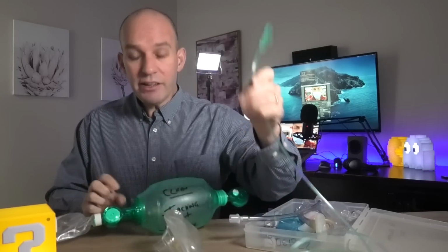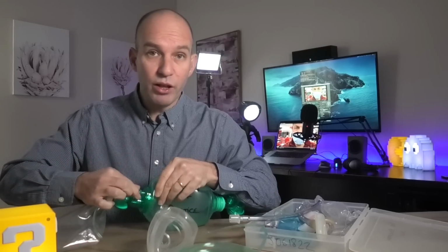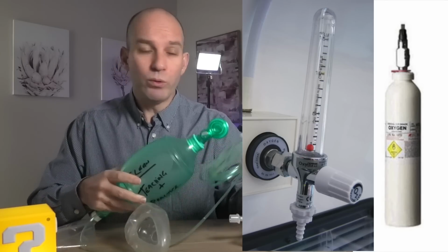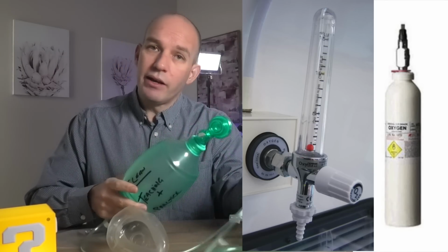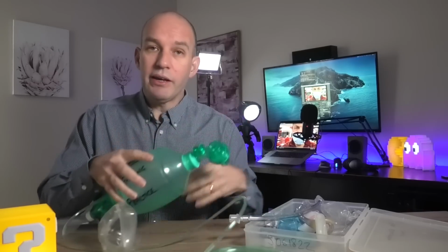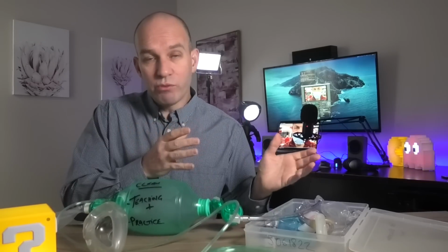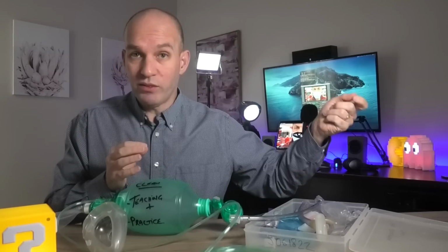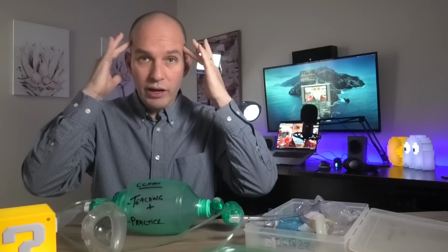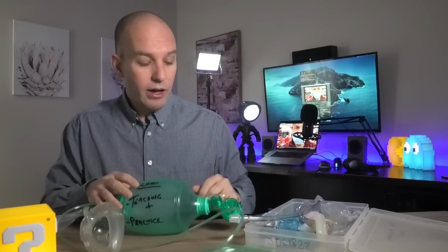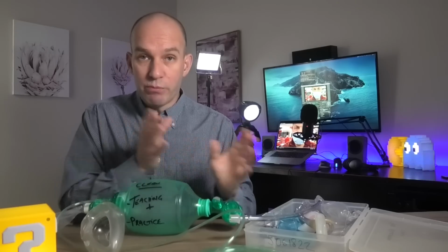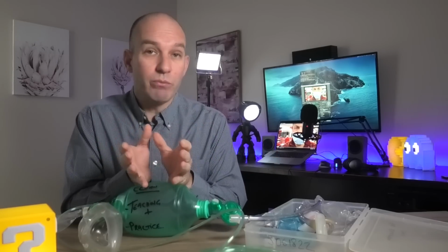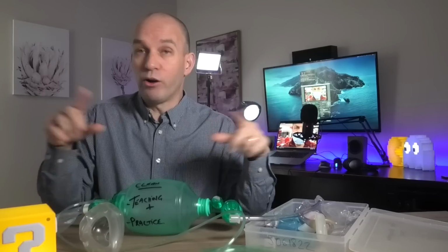There's an oxygen inlet that takes oxygen from a supply somewhere, be it cylinder, wall, whatever it might be, and that gets mixed in with a little bit of air in here and goes into the patient. In a rescue situation where you're doing CPR, you're cracking this thing to 15 litres per minute, providing hopefully 100% FiO2, that's a flow of oxygen into a patient, and that's to help keep the brain alive and the heart alive, the primary things to keep us going. But we don't want to run at 100%. You want to actually run as close as possible to 21%, which is our oxygen in the environment right now.